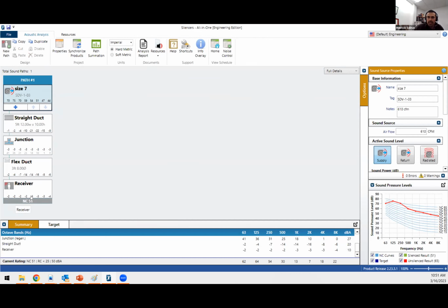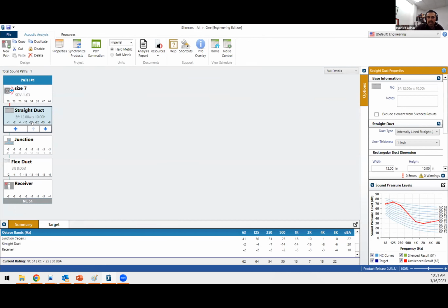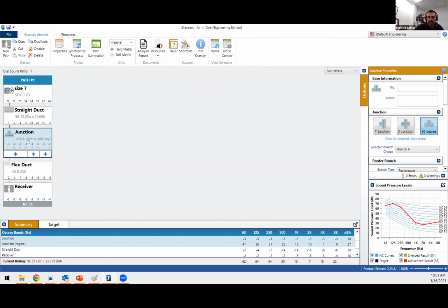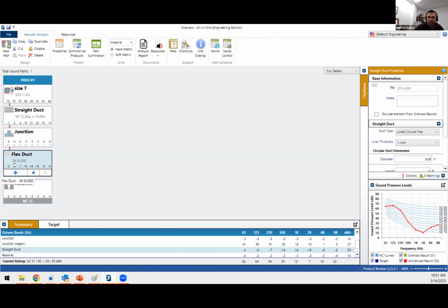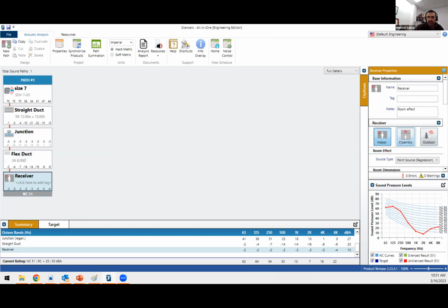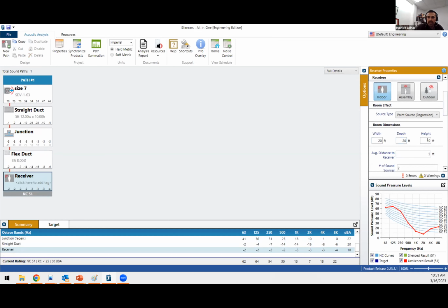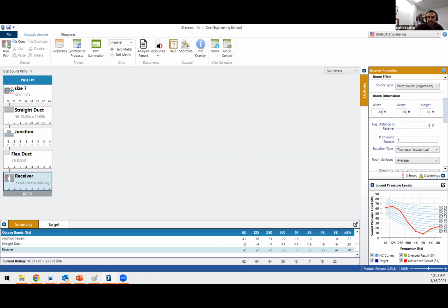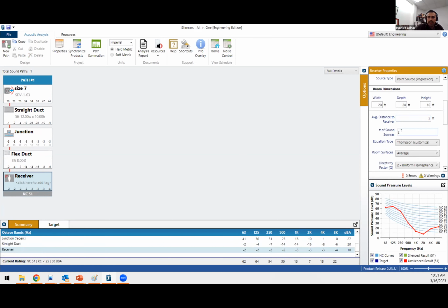Now, when you're rating terminal units using AHRI 880, it takes a lot of assumptions. It assumes 5 feet of lined duct. It assumes it has a junction with a certain amount of branches. Then you have a bunch of insulated straight duct, and then you have a 400 square feet room, or 20 by 20 by 10 foot high, with a distance to the ear of 5 feet from the air outlet with 2 diffusers or maybe more. So that is a bunch of assumptions, and you might look at it and say, oh, I'm going to be at NC 51. But that is only the rating that you see in the catalog for terminal units. It's only there so that you can compare apples to apples with other manufacturers.